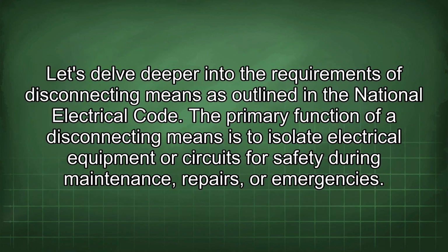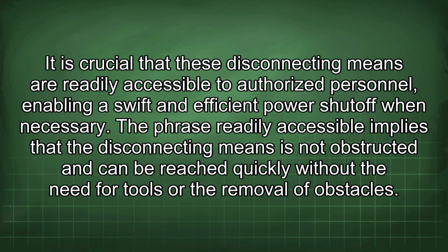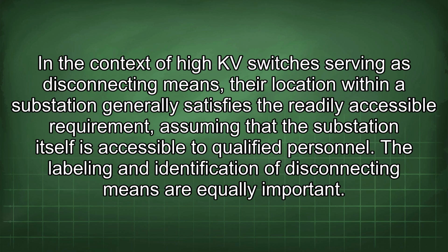Let's delve deeper into the requirements of disconnecting means as outlined in the National Electrical Code. The primary function of a disconnecting means is to isolate electrical equipment or circuits for safety during maintenance, repairs, or emergencies. It is crucial that these disconnecting means are readily accessible to authorized personnel, enabling a swift and efficient power shutoff when necessary. The phrase readily accessible implies that the disconnecting means is not obstructed and can be reached quickly without the need for tools or the removal of obstacles. In the context of high kV switches serving as disconnecting means, their location within a substation generally satisfies the readily accessible requirement, assuming that the substation itself is accessible to qualified personnel.